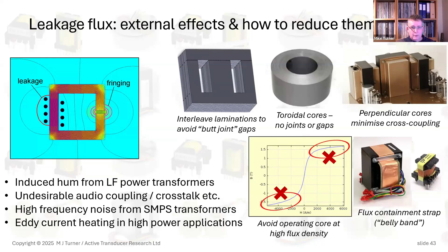And the final thing you can do is to put a strap around there. People call that a belly band sometimes. Copper foil, usually wide, to give low resistance. And the idea is that if there is any flux that leaks out of the core, it cuts this shorted turn, and that turn carries a lot of current and opposes the stray field from the transformer. You'll see that quite a lot on switch mode transformers, not so often on 50 Hertz ones, but the Japanese used to do it quite a lot.